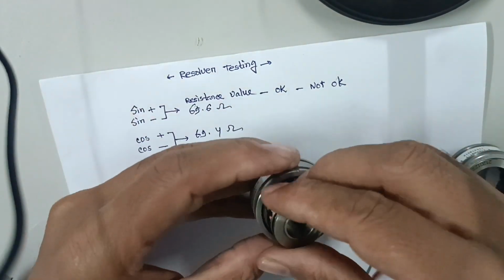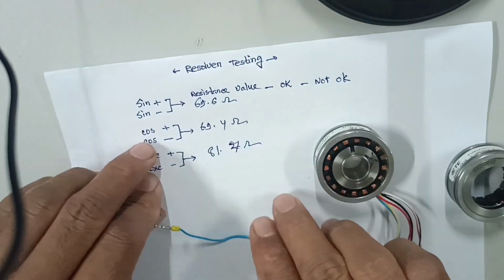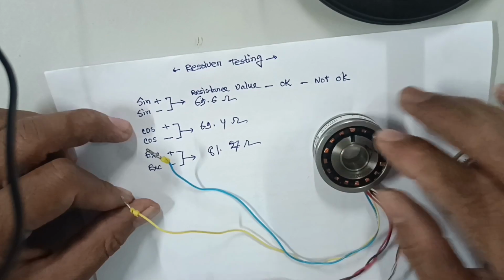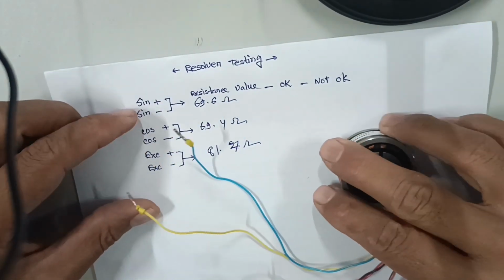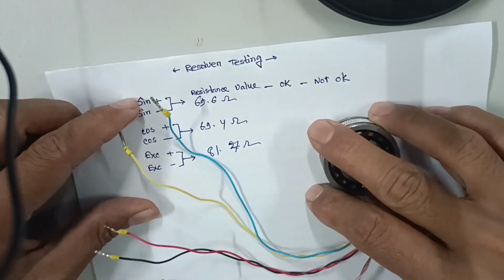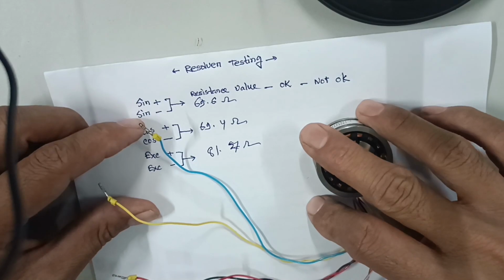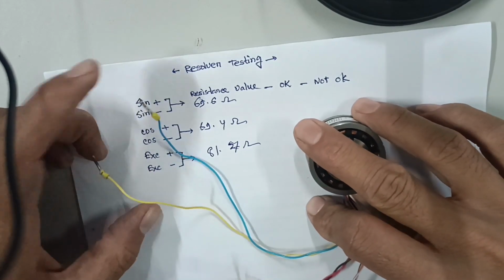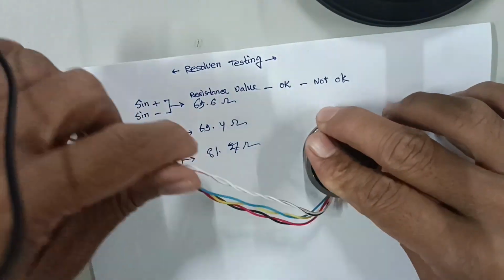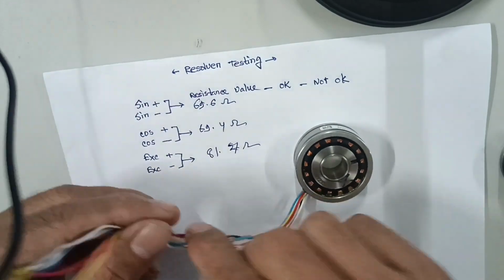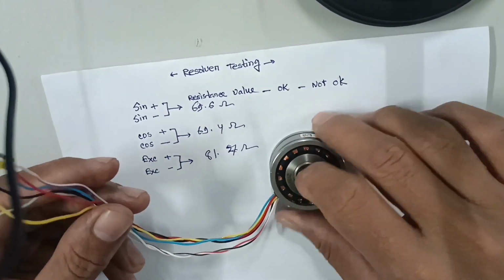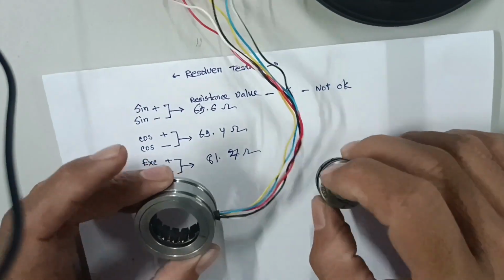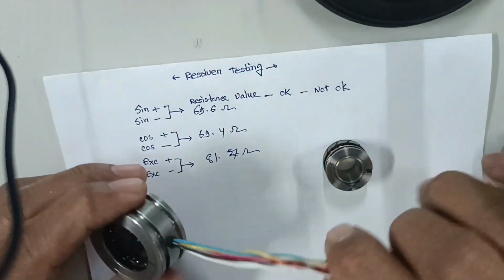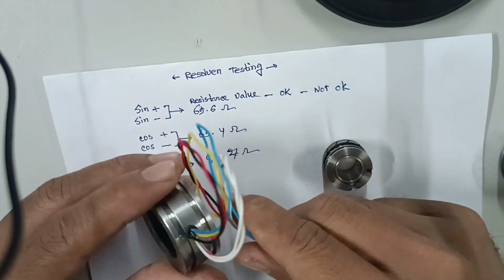Before fitting it again in your system, you must ensure which one is stator and which one is rotor, because there's a chance to interchange them - there is a serial number between the stator and rotor. You have to clearly understand that, match the rotor and stator, then fix them again in your motor. Then it will be okay.